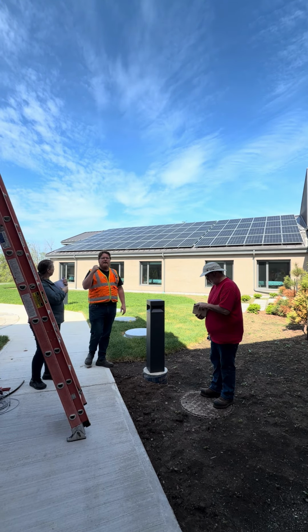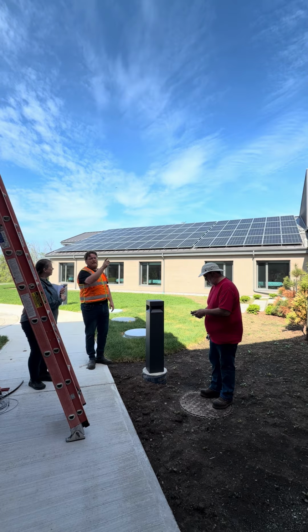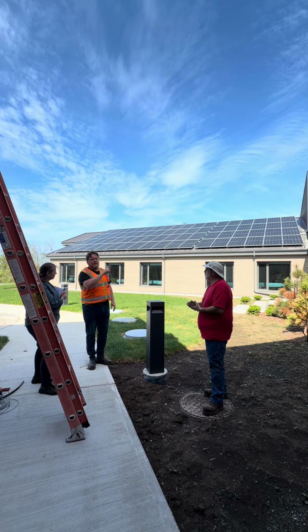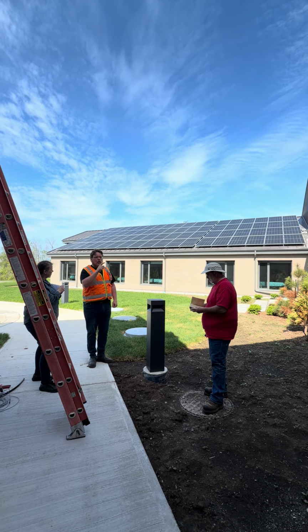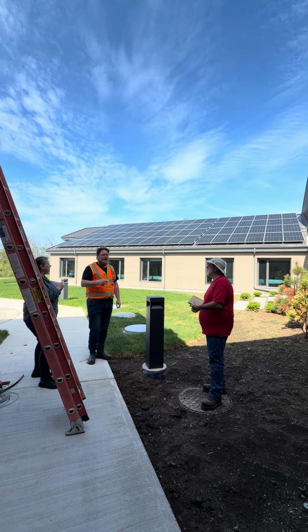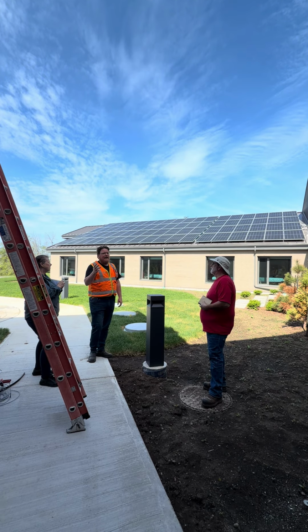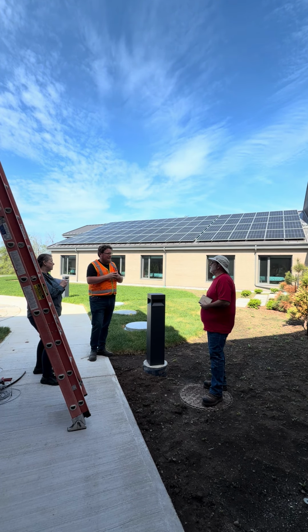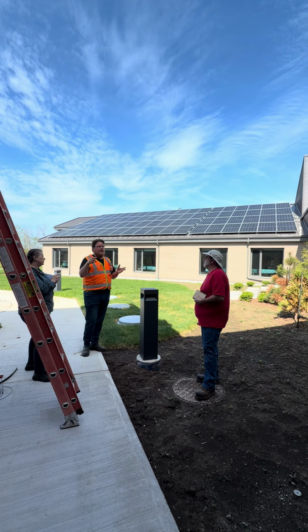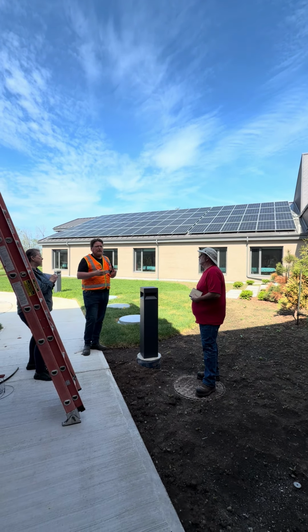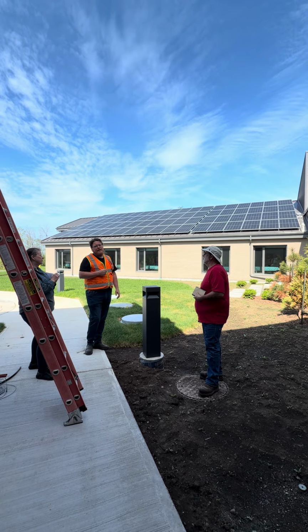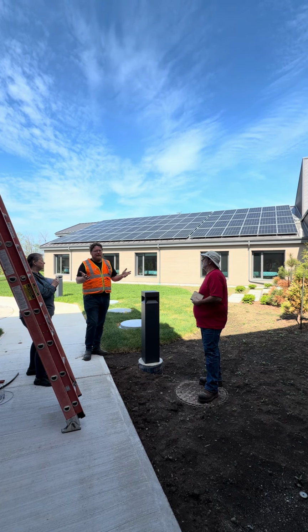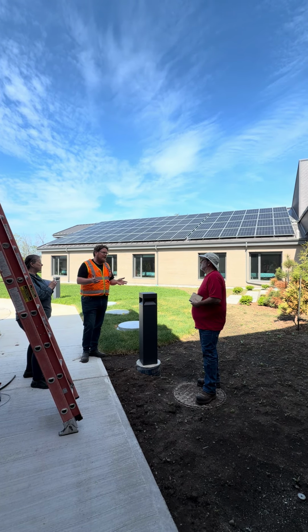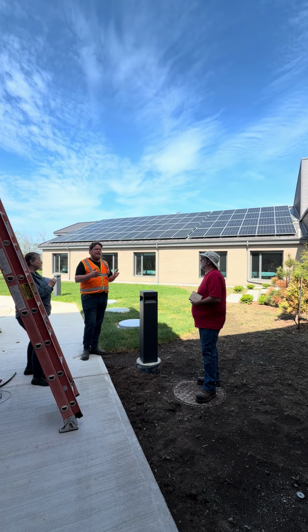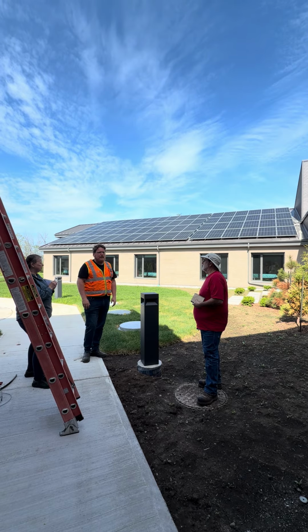When I looked at this on the weekend, there's about 430 optimizers across the site, and there's one that was reporting having difficulty, so you will get some alerts like that. It's not something to panic about. It's just something that will need to either be reset or replaced under warranty if it persists. One optimizer down on a system this large is not worth calling for a service call.